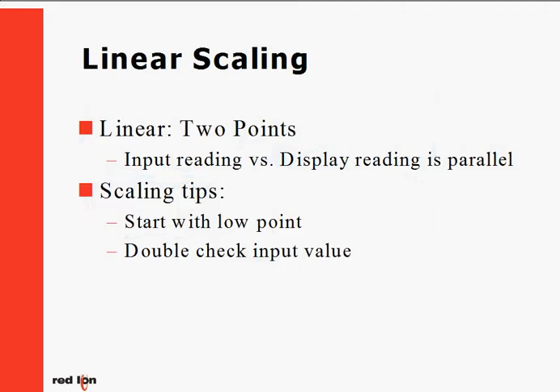Linear scaling of an analog signal is the most common type of scaling you can use to display a value different than your input. Linear scaling consists of four points: a low and high point of your input signal, and a low and high point of your display reading.